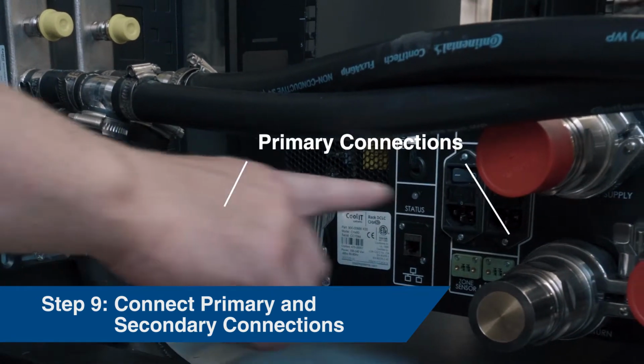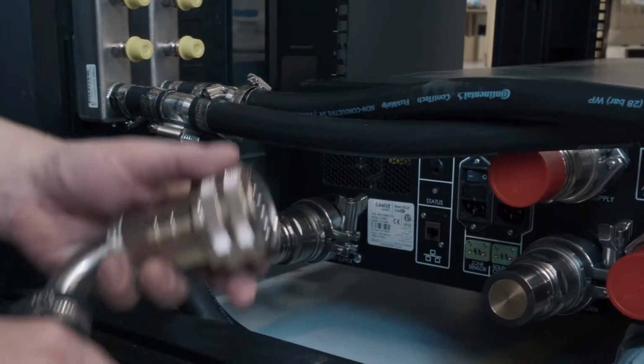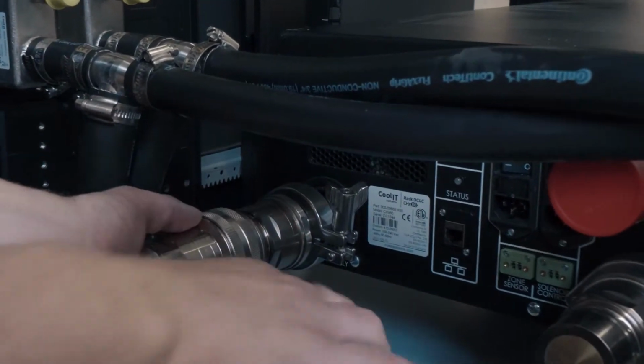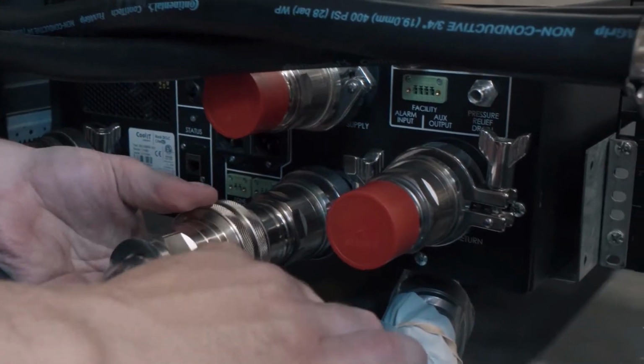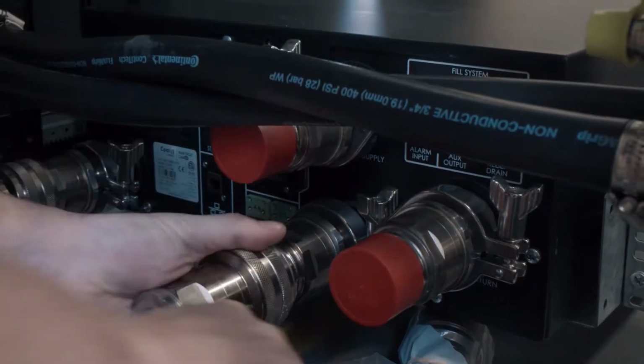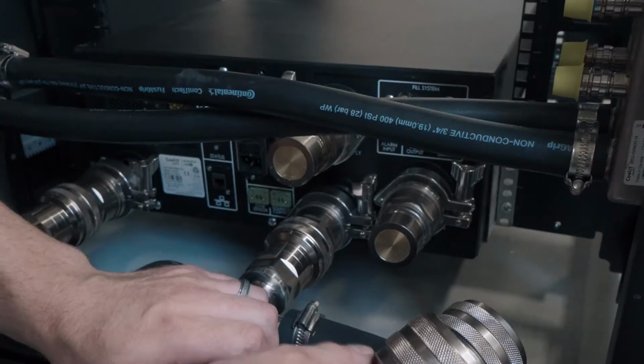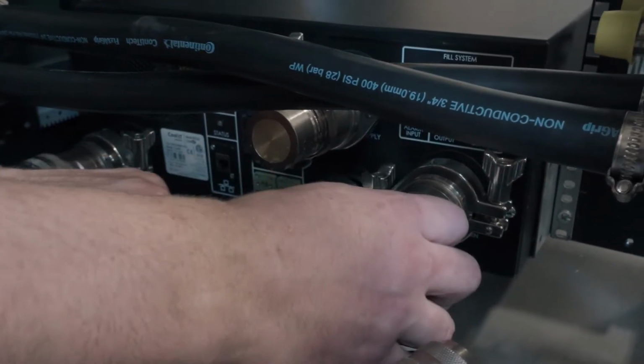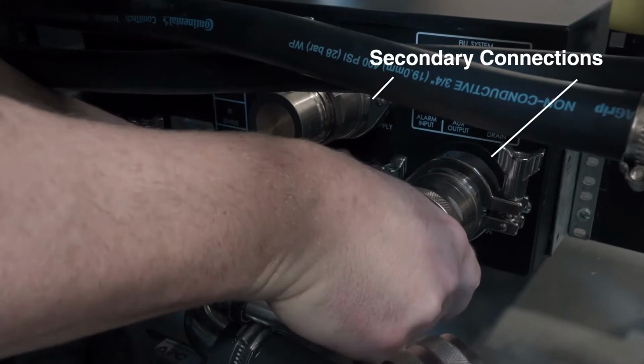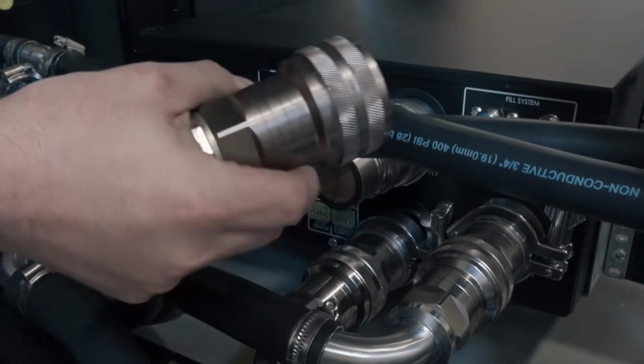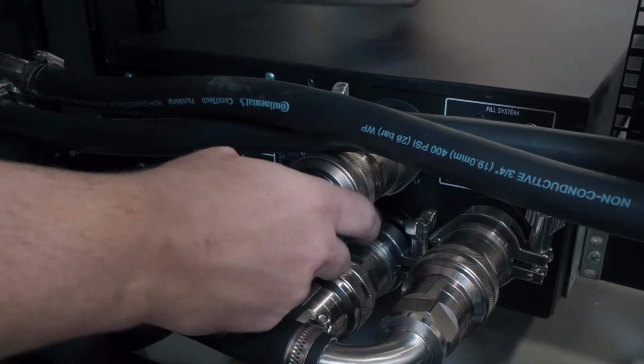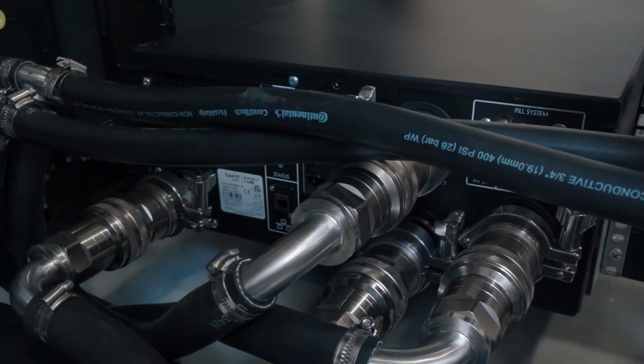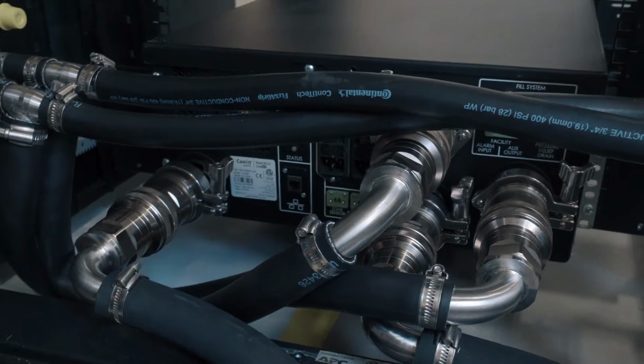Step 9. Connect primary and secondary connections. You must now connect the manifold tubing and facility tubing to the heat exchanger. Locate the quick disconnects attached to the manifolds and facility tubing, pull back on the quick disconnect collar, and push it onto the corresponding plugs on the heat exchanger. Next, take the facility side connectors and connect them to the heat exchanger. It is important to connect the supply and return lines to the correct positions on the heat exchanger. Note that the facility valve must be opened to allow fluid to travel to the heat exchanger.